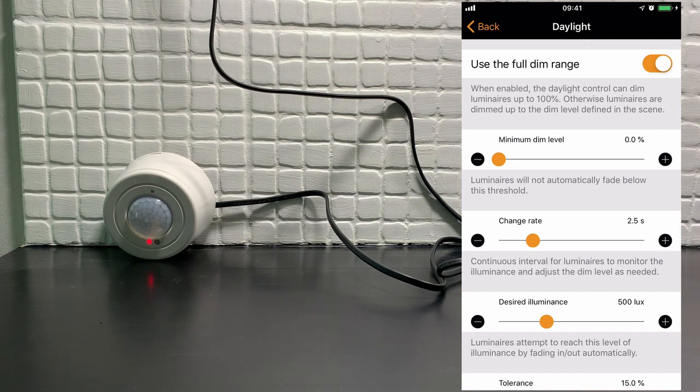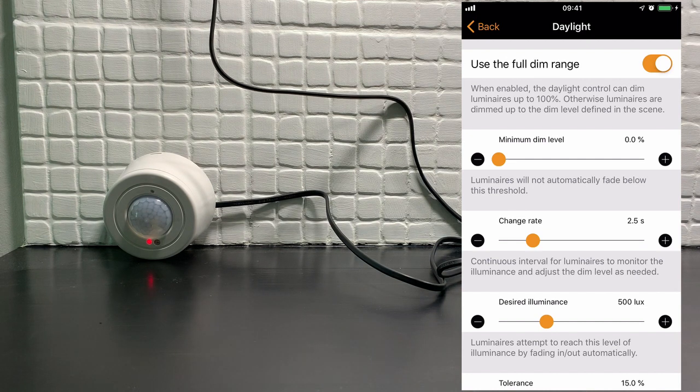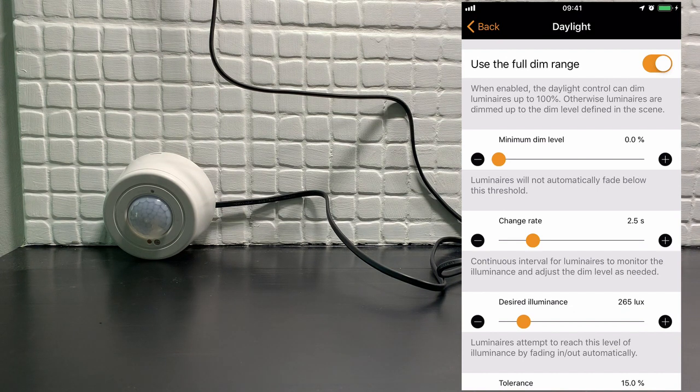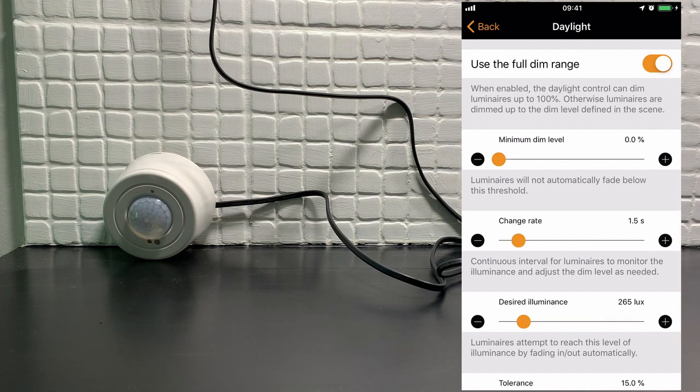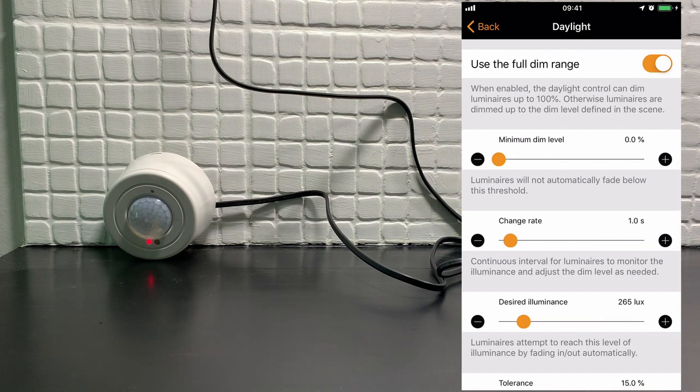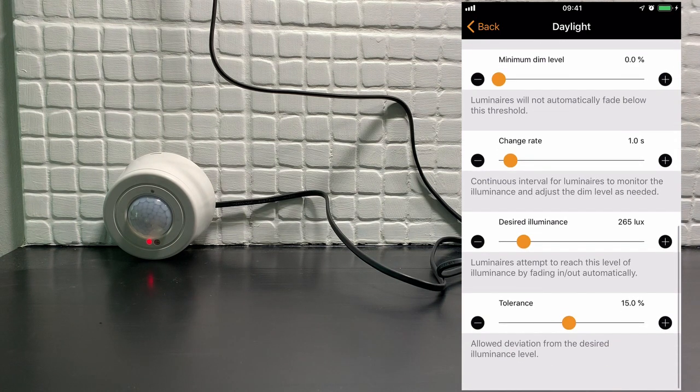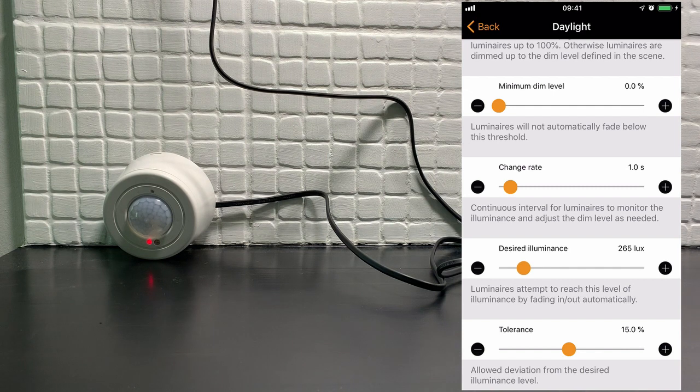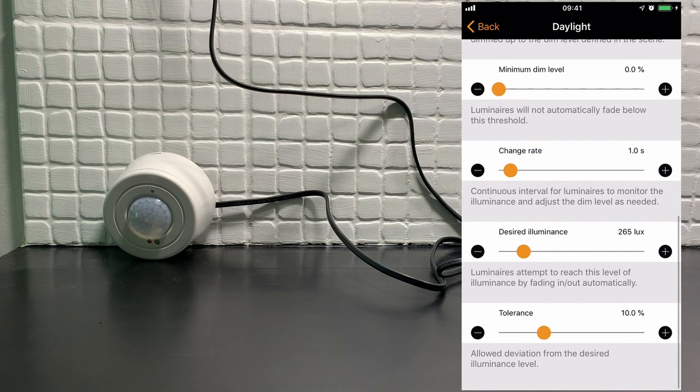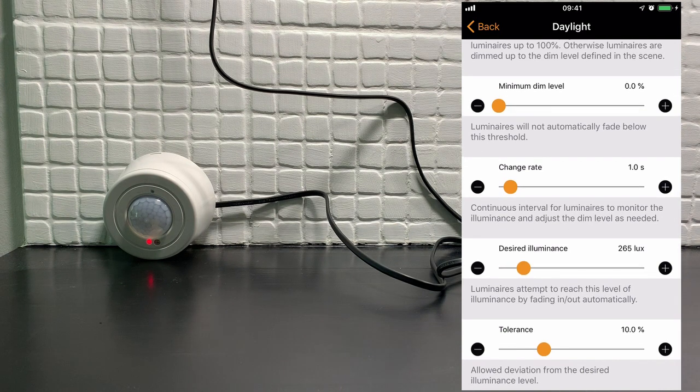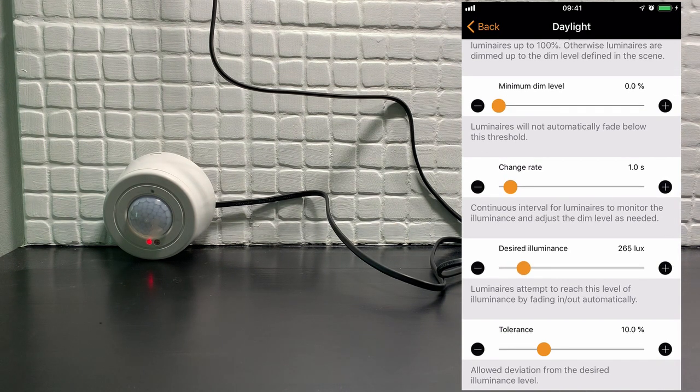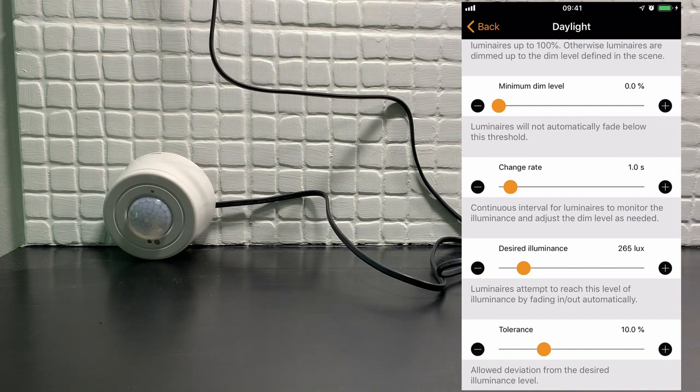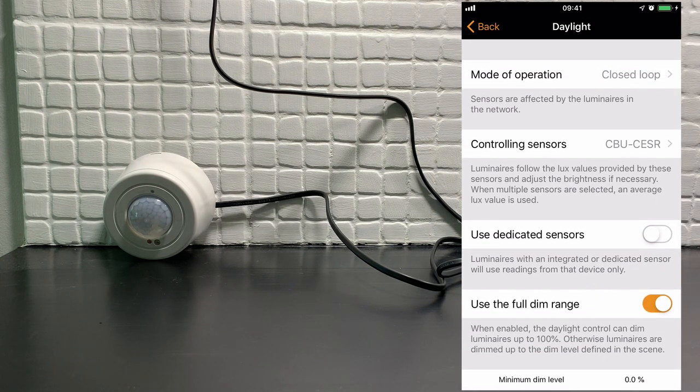The default value is 500 lux. Let's lower that down to around about 265. For this demonstration, I'm also going to lower the change rate to one second. The change rate is how often the sensor looks for a change in the value of the light coming onto it. Tolerance, I will also drop to 10%. Tolerance is there to select how far away you can deviate from the lux value, in this case 265. Once that's done, I can select back.